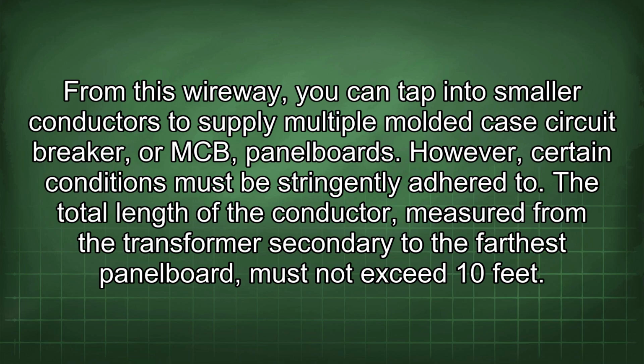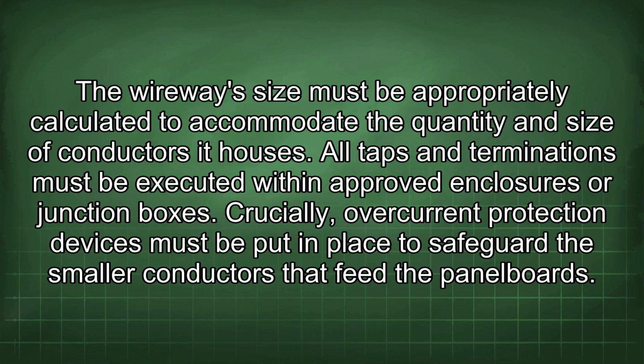The total length of the conductor, measured from the transformer secondary to the farthest panel board, must not exceed 10 feet. The wireway size must be appropriately calculated to accommodate the quantity and size of conductors it houses. All taps and terminations must be executed within approved enclosures or junction boxes. Crucially, overcurrent protection devices must be put in place to safeguard the smaller conductors that feed the panel boards.